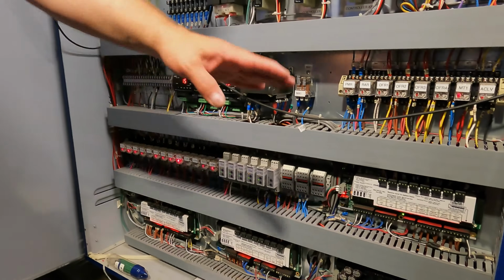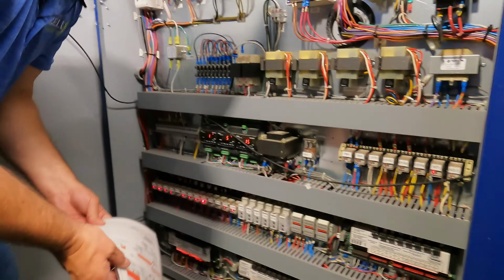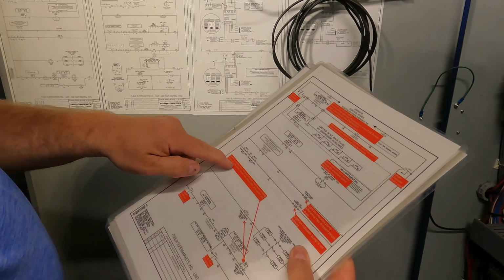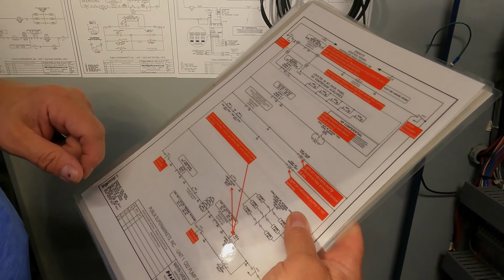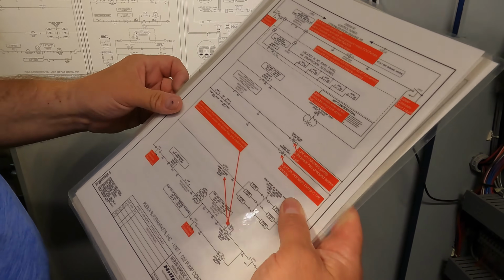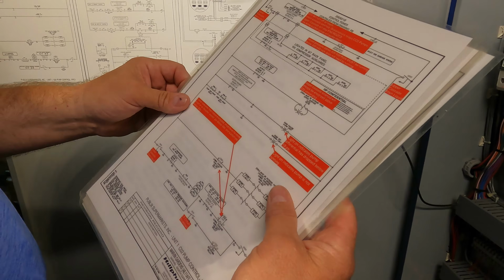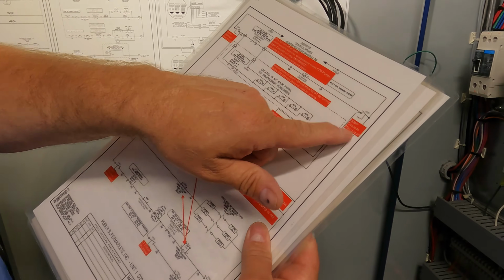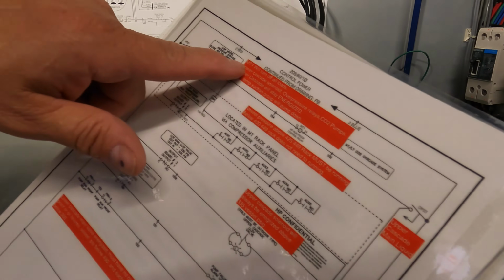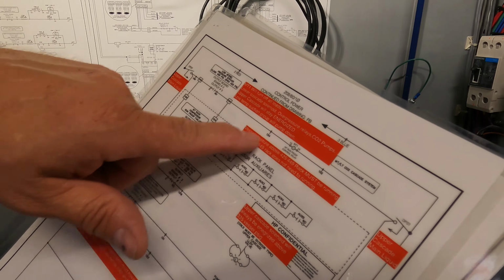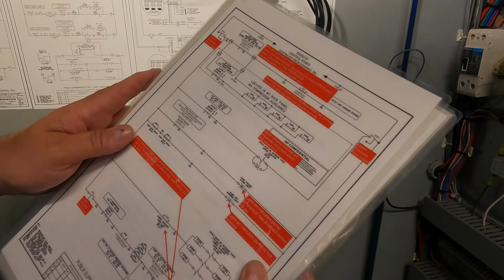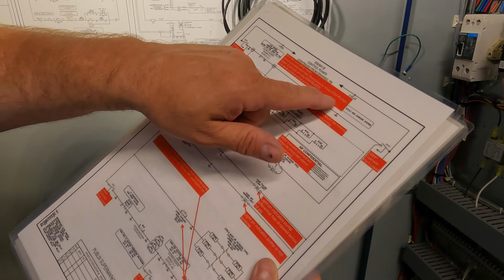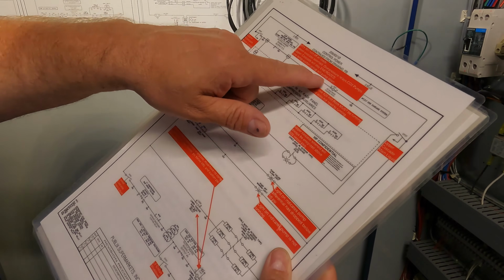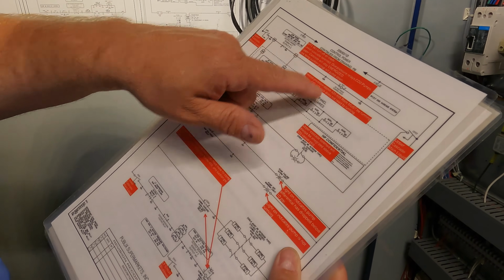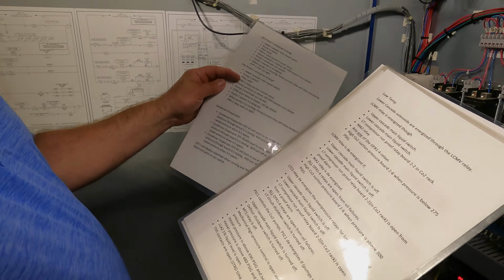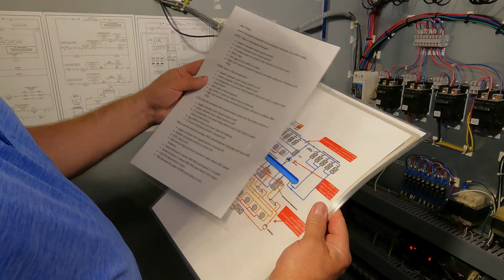These are all of our safety relays. One thing we did, we came up with these sheets and we put points on there to tell you what it's doing. That way, when guys are in here trying to diagnose something, they can see what's going on. Like here, we've got the upper cascade main switch, and we put notes in there. MT1 will turn off all loads. The lower cascade solenoid, overpressurized relays, and CO2 pumps, the upper cascade will stay energized, but the lower temp suction group will pump down. And this helps everybody out so much.